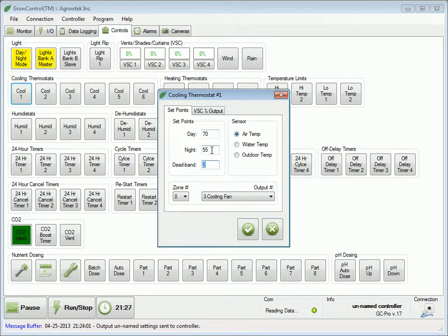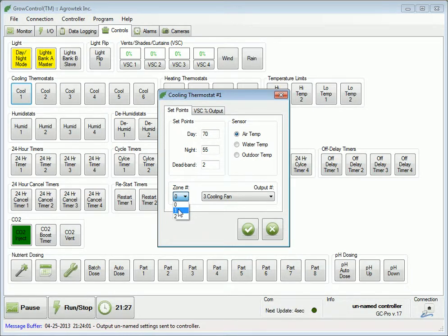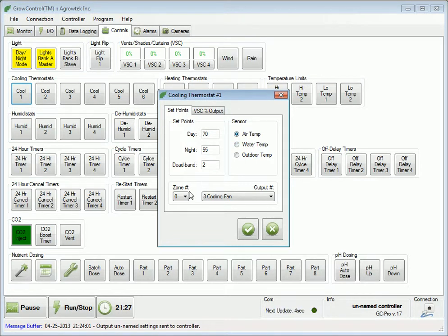If our controller is configured for multiple or dual zone use, we must select the zone. Zone 0 defaults to number 1 by default. If we have a second climate sensor and want this cooling thermostat to respond to those temperatures, we must select zone number 2. By default, this thermostat responds to the air temperature in the selected zone. If we want it to respond to water temperature or outdoor temperature, we must make that selection here.